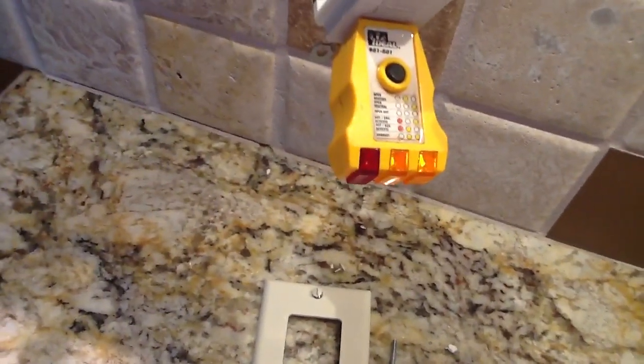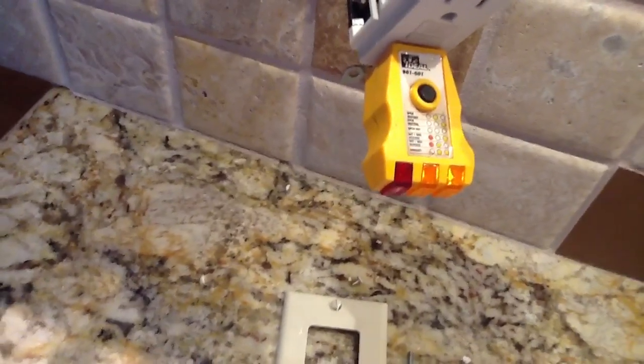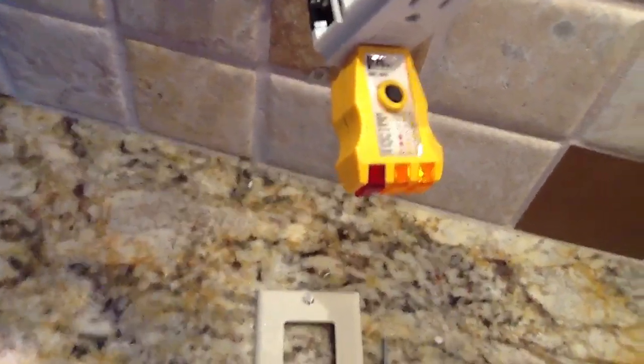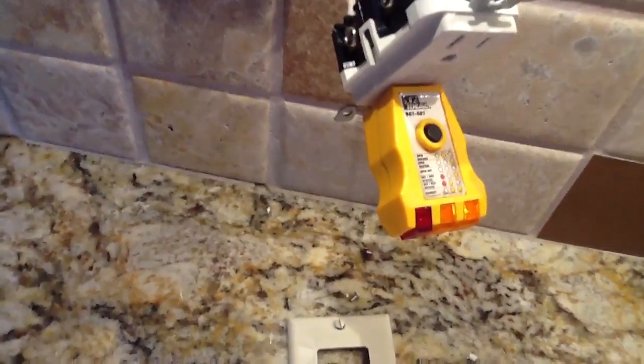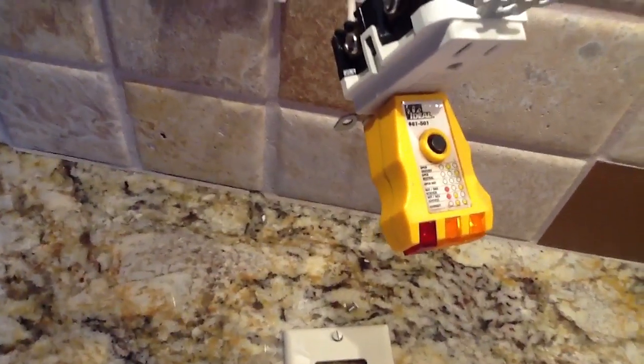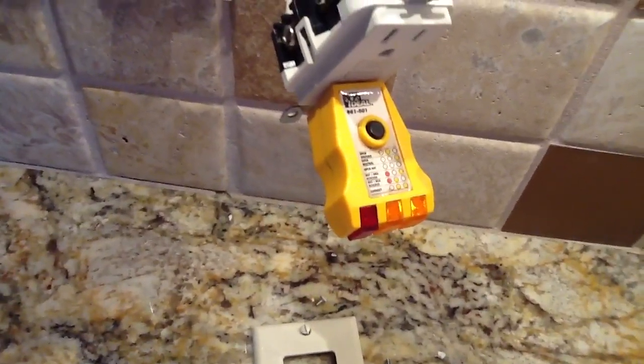The fourth way is an installation defect. As soon as you turn it on, the GFI trips. That means there's no load — the neutral wires are crossed between the line and load side. You just need to check and make sure you get your wiring straight.